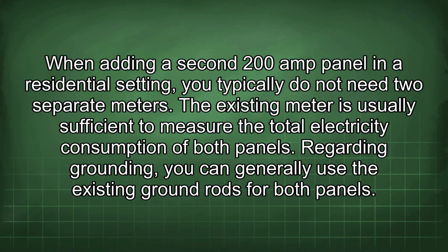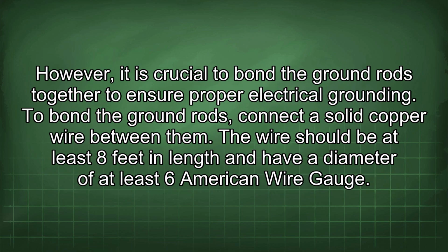When adding a second 200 amp panel in a residential setting, you typically do not need two separate meters. The existing meter is usually sufficient to measure the total electricity consumption of both panels. Regarding grounding, you can generally use the existing ground rods for both panels. However, it is crucial to bond the ground rods together to ensure proper electrical grounding.